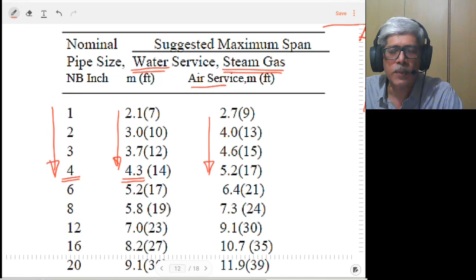So, for example, if it is a 4-inch pipeline for water service, you need to have the supports less than 4.3 meter span. So this is the maximum span, and the calculations are done for the stresses because of the self weight of the piping. So this span takes into account only the stresses due to the self weight, that is the weight of the piping and weight of the fluid, in this case water. So under the action of these two, if you provide 4.3 meter span, then the bending stresses over that span will remain in control. So that is what this particular thing means.